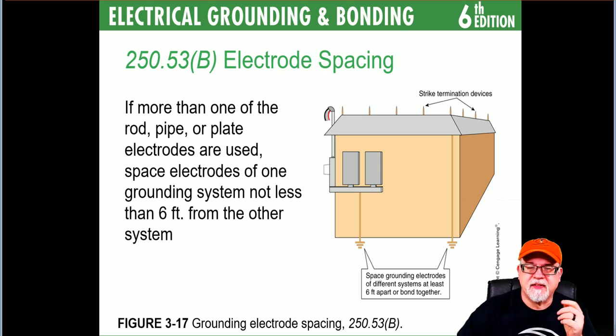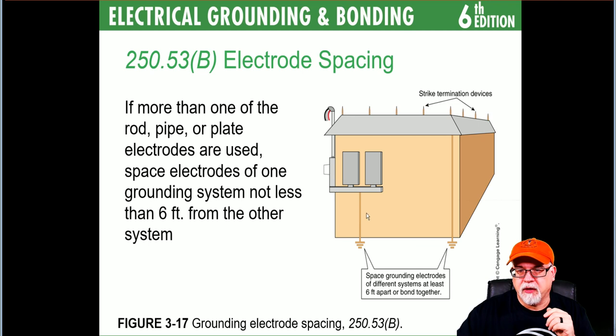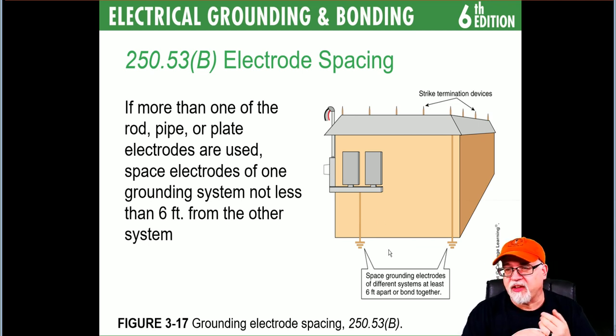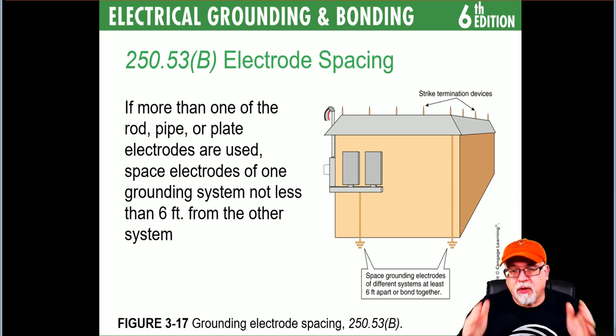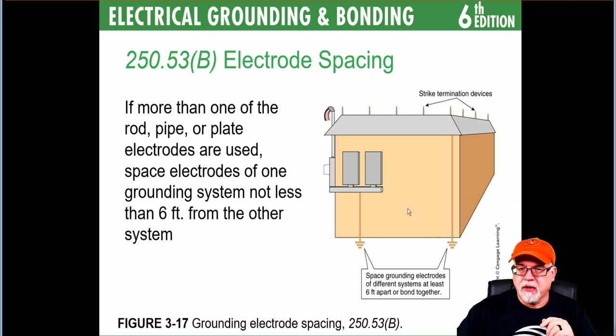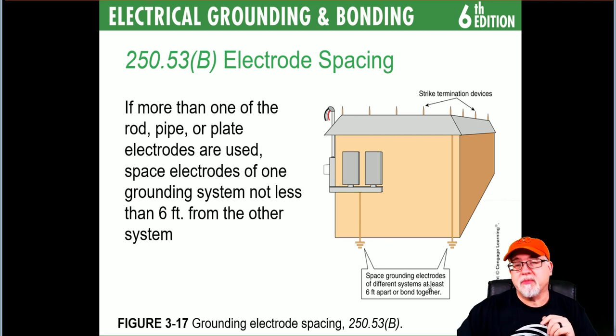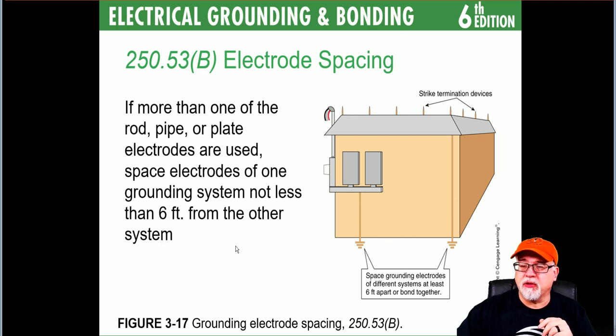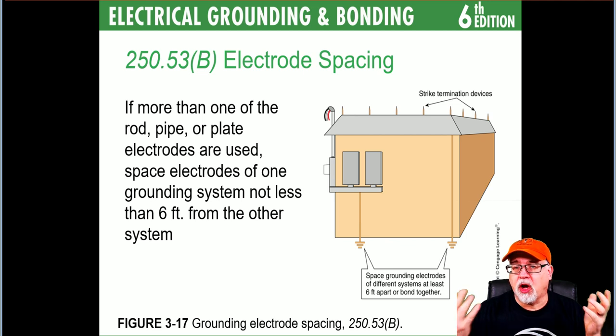250.53(B) — electrode spacing: if more than one rod, pipe, or plate is used, they must be at least six feet apart. This also applies when you have electrodes for a separate lightning protection system — those electrodes would also need to be at least six feet apart, or you bond them together. Most of the time I use one set of electrodes and bond all systems together to utilize those same electrodes.